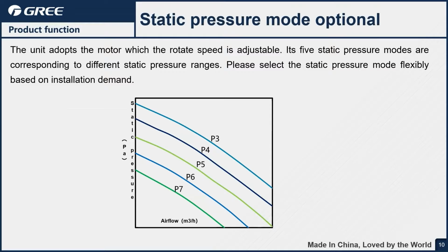The unit does come with 5 static pressure settings. We can get up to 1 inch static pressure, or up to 0.8 inches of static pressure with a heat kit installed. So again, for most applications, we're going to have plenty of airflow to suit your needs.